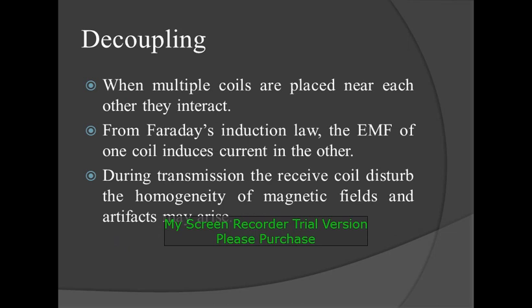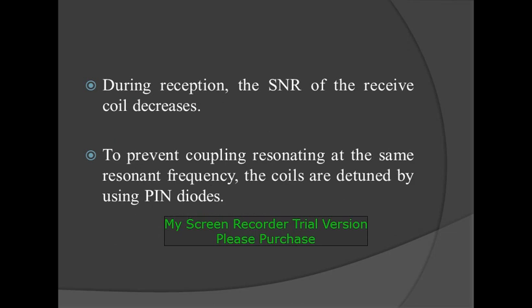Decoupling: when multiple coils are placed near each other, they interact. From Faraday's induction law, the EMF of one coil induces current in the other. During transmission, the receiver coil disturbs the homogeneity of the magnetic field and thus artifacts may arise. During reception, the SNR of the receiver coil decreases. To prevent coupling at the same resonant frequency, the coils are detuned by using a PIN diode.